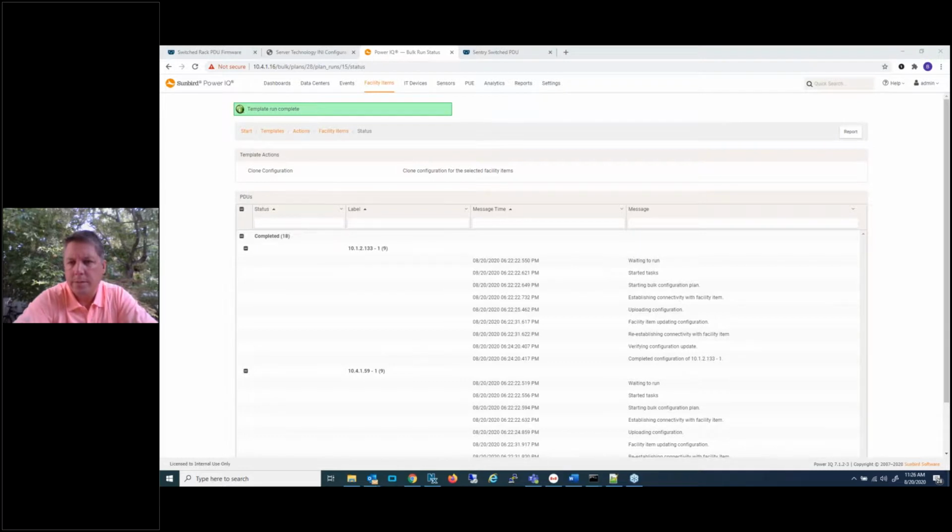And it is only for the PRO1 and the PRO2 series PDUs. The earlier cabinet distribution unit series products do work with the startup stick that I showed at the beginning, but they do not have the Server Technology INI configuration file format support. So PRO1 and PRO2 series PDUs are the PDUs that run the version 8 firmware. So with version 7 firmware, you would just use the startup stick? Well, just to bring it up online on the network, there are other options you need to use for doing mass configuration.